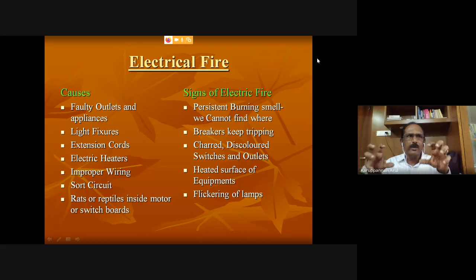Charred, discolored switches and outlets. The fire may be for a short time and may char and discolor the switches and other things. The fire would have put itself off. But in the course of time, this charring occurs again and again, and one day the fire will break out in a huge way. So if we check these switches and outlets and there is charring or black color or discoloration, we have to attend to it, find out what is wrong in that area and repair it.